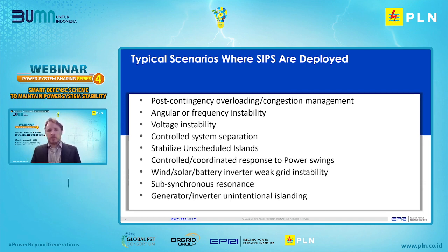As mentioned by the previous speaker, there are a lot of different cases or scenarios where these schemes are deployed, such as overloading, frequency instability, voltage instability, controlled system separation. In more recent times, with a lot of wind and solar and battery inverter technologies coming on, where they connect to weak parts of the grid with low short circuit level, more schemes are being deployed to prevent weak grid instability, where the inverter may lose stability due to low short circuit levels. So these are becoming more common as well.